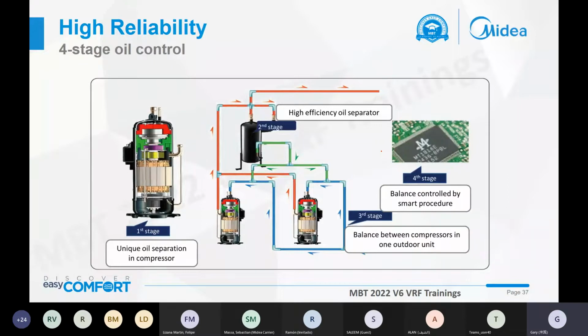And this part is for the oil control. As we know, the oil control is very important in our VRF systems. If the oil control is not good, the compressors will easily break down. We have 4 stages. The first stage is the oil separation in the compressors. As you know, we use famous brand compressors, Hitachi. It is a famous brand in the world.